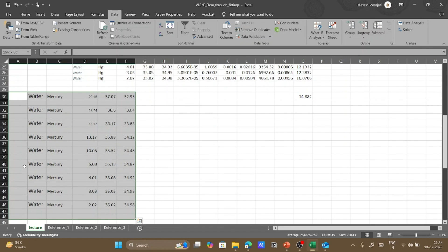So first we know the flow rate, and we know the manometric head, so convert the flow rate from liters per minute to meter cube per second. So we have applied that conversion, right. Then compute the velocity. So velocity is flow rate divided by your area. And how is the area calculated? π/4 d square, where we have to consider the actual diameter. Okay, so don't forget this. So what we selected is the pipe nominal diameter, but the actual diameter is the inner diameter that we have to select for the calculation, right?